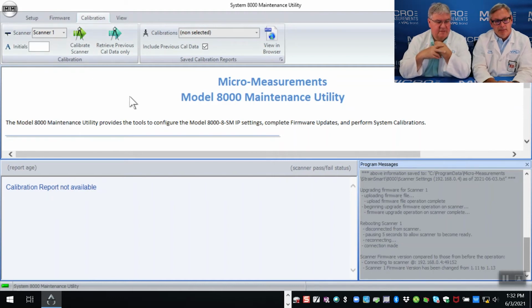One more thing I want to add is that typically when you calibrate the box, I would recommend that you disconnect the inputs from the box, because the voltages actually come from the VCal card. And I have had customers before that experienced issues calibrating the scanner when they had their inputs connected because they had a path to ground that they weren't aware of. So if you're going to calibrate your 8000 scanner, just take a few minutes, disconnect your inputs, and then calibrate the box. And assuming it passes, then you can reconnect your inputs and take off with your testing. Good point. Good point.